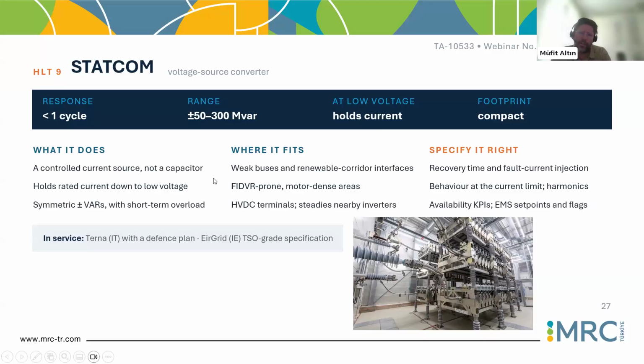Where it fits: if it is a very weak condition, a weak bus, or if you need fast control, or if you need reactive current during the fault to operate the protection devices in a better way, it's important to use this device. Around wind farms, you can use high voltage DC connection points, depending on the requirements from the grid operator. Since they are expensive, you need to design it very carefully and use it very efficiently after installation. We can continue.